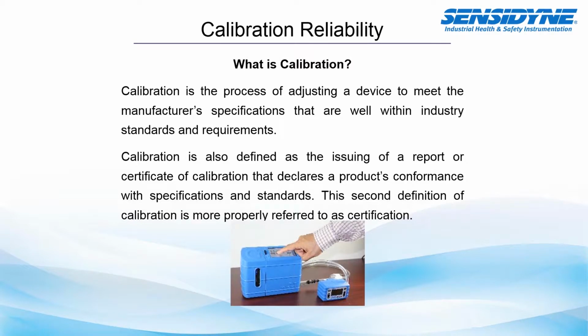So to begin, we really need to focus on what is calibration. Calibration is actually adjusting a device to meet the manufacturer's specifications that are within the industry standards and requirements. Most of us think of calibrating as setting a flow rate on an air sampling pump. While this is very true, calibrating really is making sure that when we set the flow rate to whatever flow rate, let's say 2 liters per minute, that 2 liters per minute is really representative of a true 2 liter per minute flow rate.